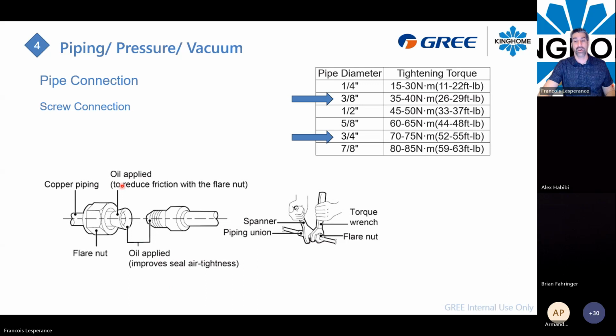Also, you can use oil to reduce the friction when you apply the pressure to make your flare connection tight enough. Most of the time, we apply too much pressure on a flare, and that can cause the flare to crack, because the torque is too high on the flare. By using the torque wrench, you will avoid that, and you will make sure you apply the right amount of pressure for a 3/8 flare, and the same thing for the 3/4 flare.